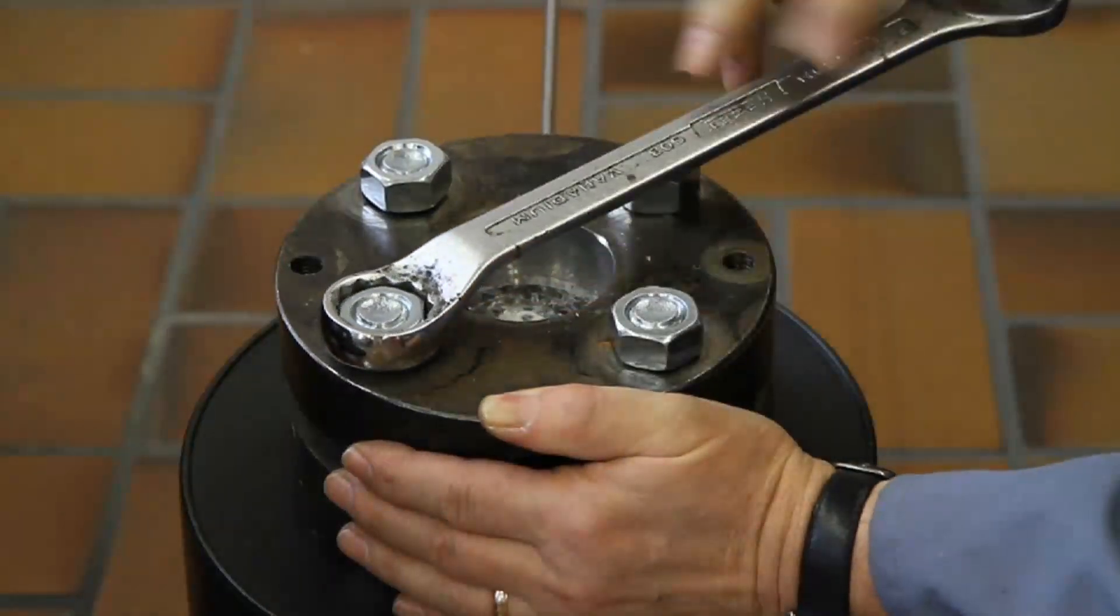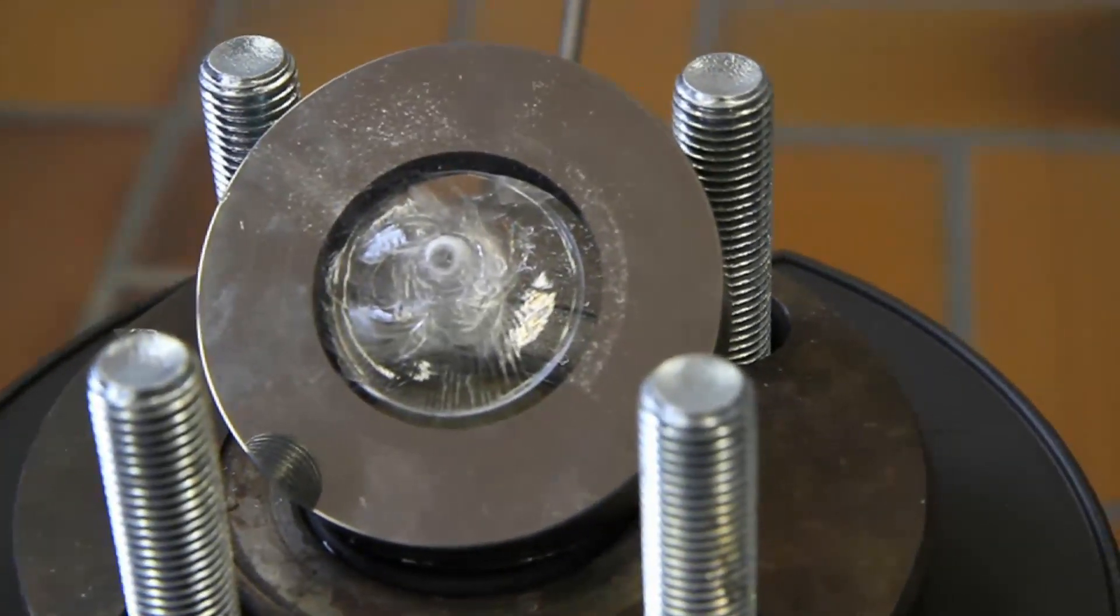With the pressure off, the nuts are removed and the test fixture is disassembled. Look at this remarkable sight glass. There are cracks on the surface, but the integrity of the glass has not been compromised.